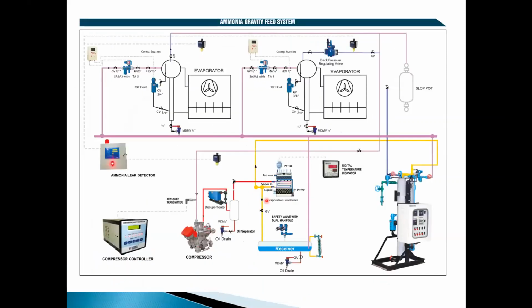Then we have the natural circulation systems, or ammonia gravity fed systems. As we were talking about, you have a similar plant: a compressor, and the discharge of the compressor goes to the condenser, where it is condensed and the liquid gets accumulated in the receiver. Now this receiver normally has a high pressure, something around 12 to 14 kg per centimeter square, depending on your ambient conditions.